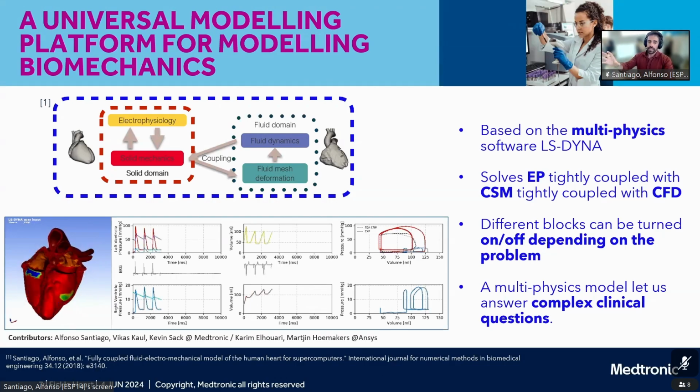And now I'm going to show a little example, in some more detail, of one of the models that we have at Medtronic. We call this a three-physics model. We have the electrophysiology that is being bidirectionally coupled with the solid mechanics, and that solid mechanics is coupled also with the fluid dynamics. So what we can do basically is replicate the different signals that we can extract from the heart, right? In this case, this model is based on LS-DYNA, and you can turn on or off different blocks depending on the problem that you're trying to solve.